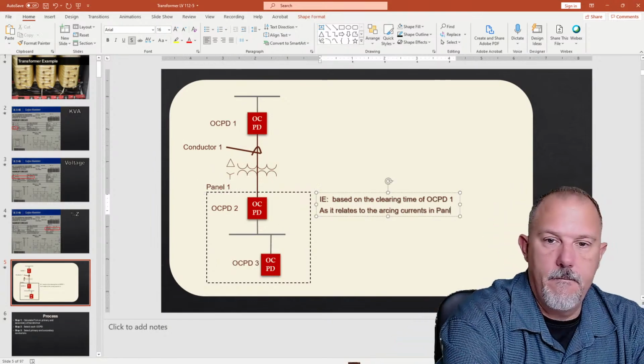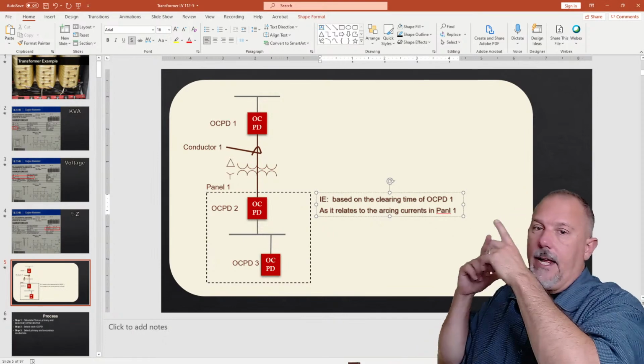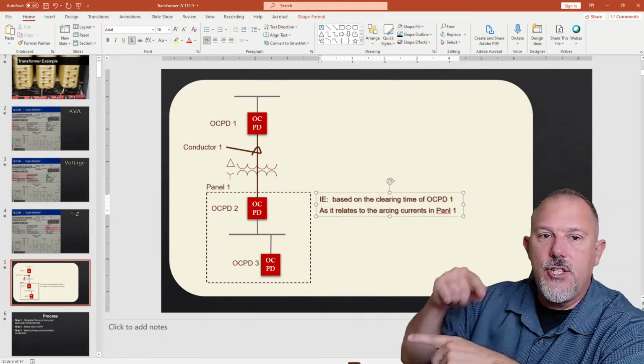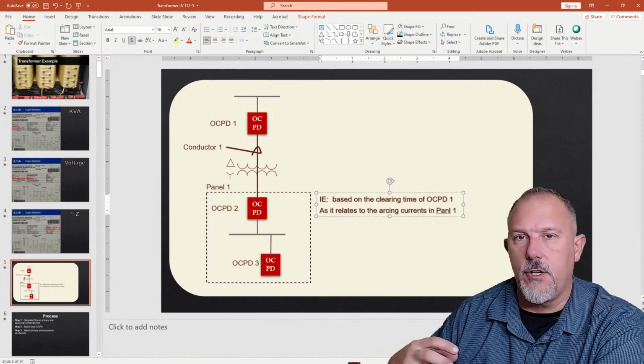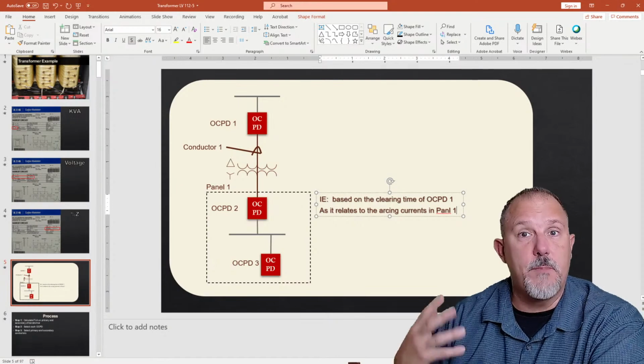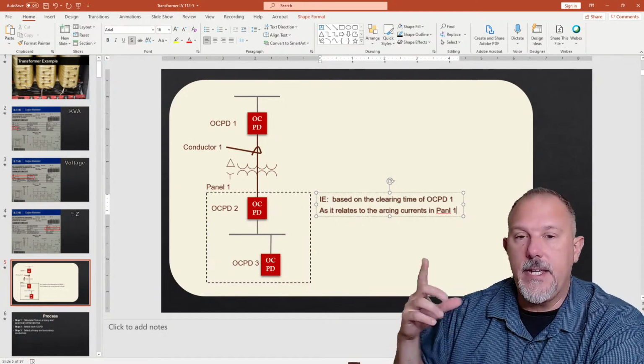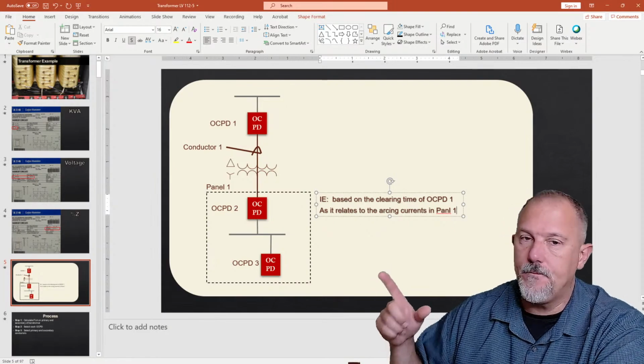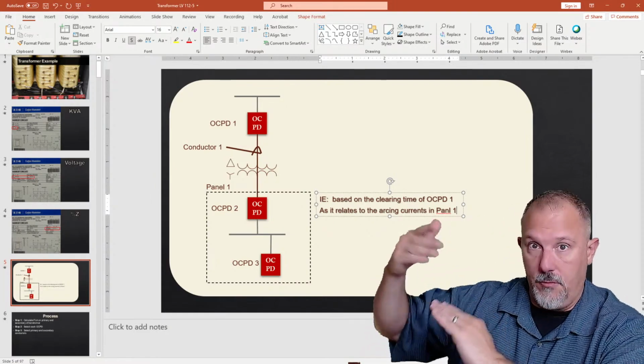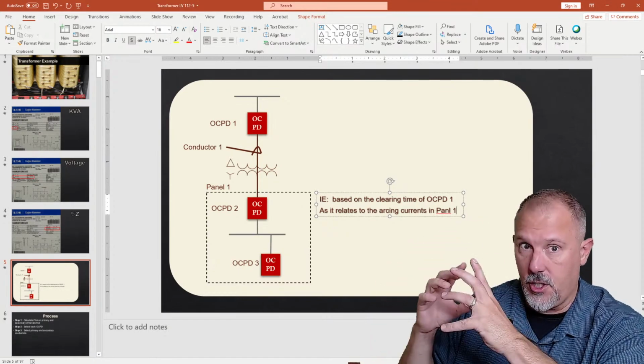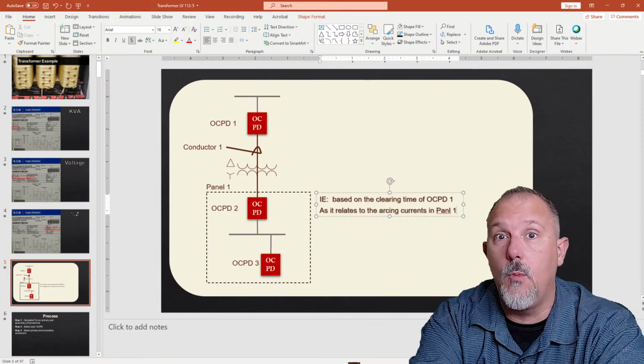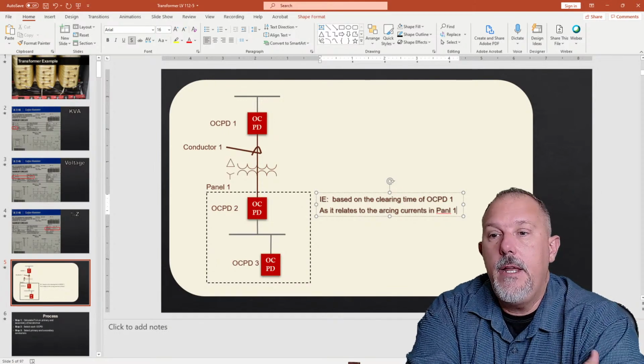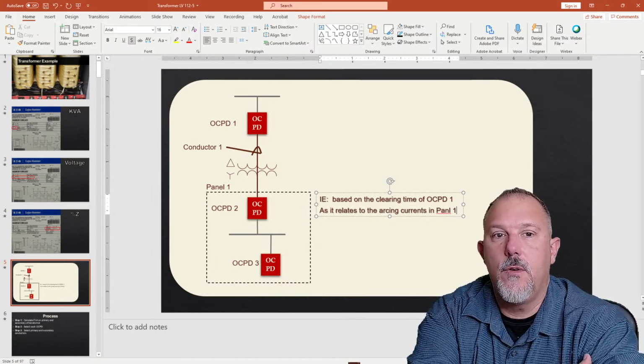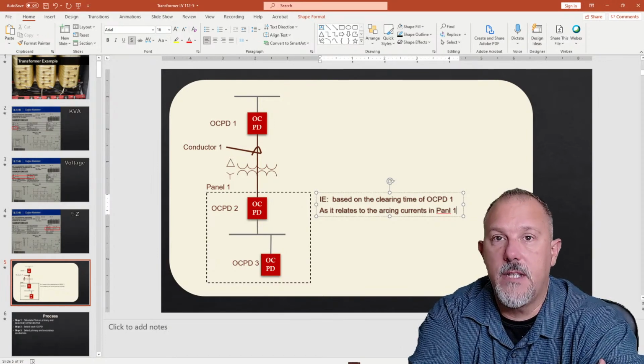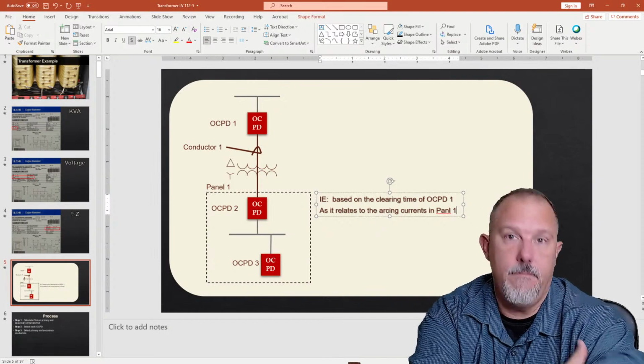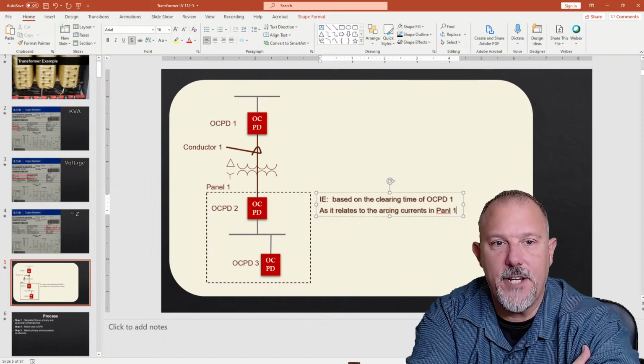In panel 1. So for me to determine the incident energy of this piece of equipment, I don't take OCPD 2, which is the main overcurrent device, and determine my arc flash values based upon the clearing time of that device. I have to calculate the arcing currents in this piece of equipment and then reflect that through the transformer and look at the clearing time for those currents based on overcurrent protective device number 1. So if my arcing currents will respond to overcurrent protective device number 1 quickly, then I will have a low incident energy in panel 1.